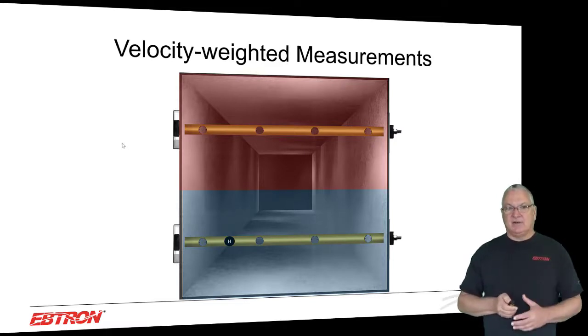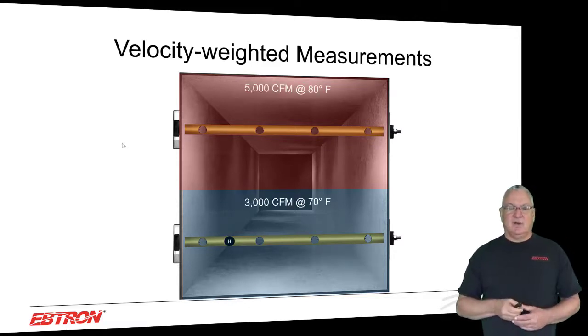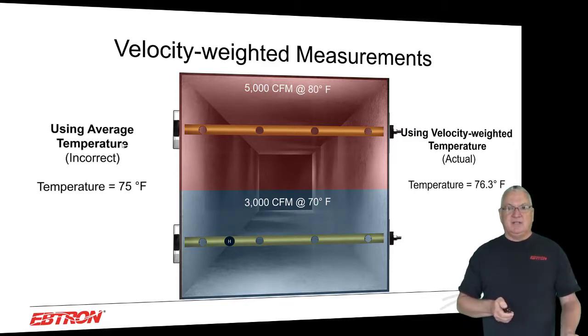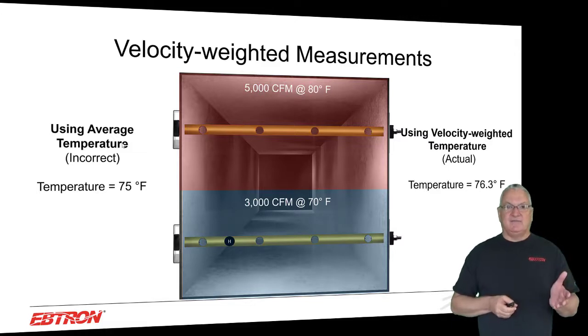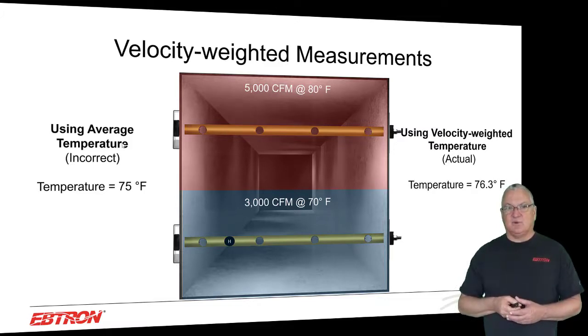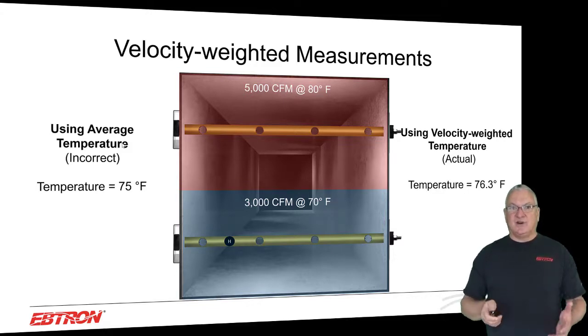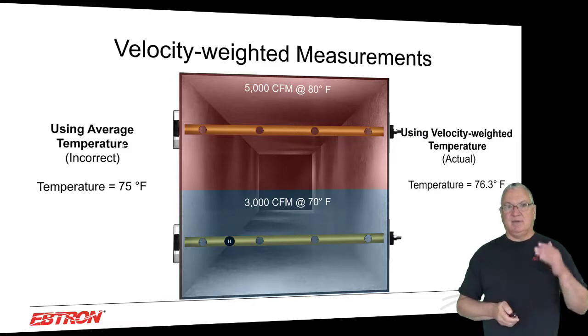But let's say we have this airstream here, and the two colors represent the fact that we have two different temperatures and two different velocities. The top of the airstream, where the first probe is, is 5,000 CFM at 80 degrees Fahrenheit, and the bottom is 3,000 CFM at 70 degrees Fahrenheit. If you simply use the average temperature, you would get 75 degrees, but the true average temperature is 76.3 because you have twice as much air moving at 80 degrees. You can't get that measurement with just an averaging temperature sensor. You need to know the airflows. That's very, very important and not obvious to everybody. And the bigger the temperature profile and the bigger the velocity profile, the more important this is.